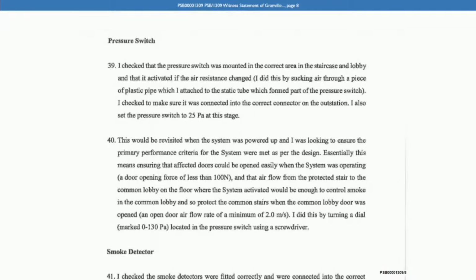Well, in the commissioning report, it says pressure switches 1 to 24, if that's what it was. And then it says operate, okay. In other words, when the pressure changed, did the switch operate? The answer is okay to all those 24 switches. Right. And there was no damage to any of the pipework or the switches or the boxes that they're held in. And that it passed. And that reference is to PS01 to PS24. I could have written PS01, next line, PS02, next line. But again, this were a document that they wanted the following day, basically.